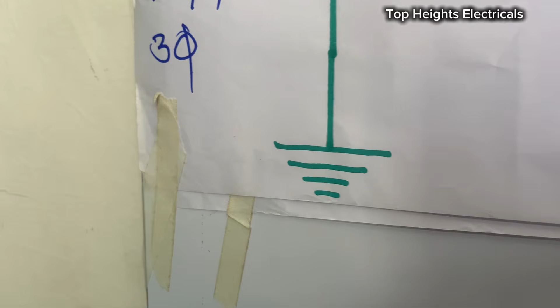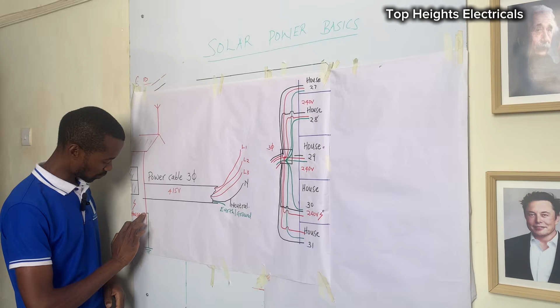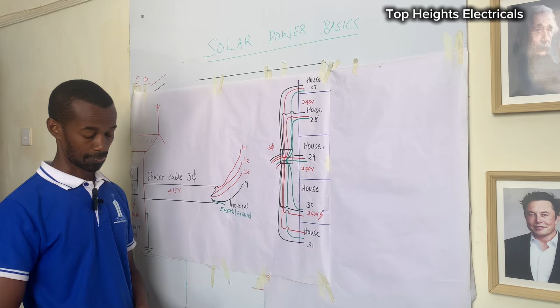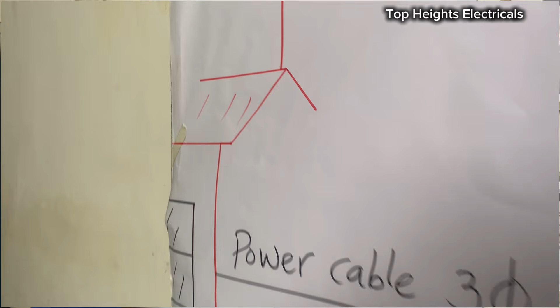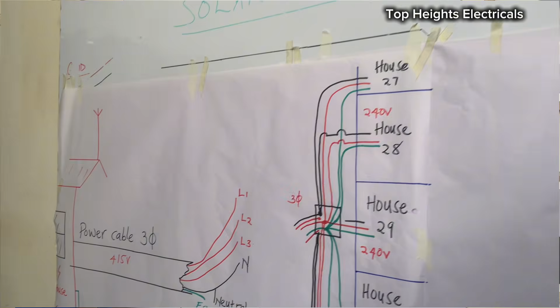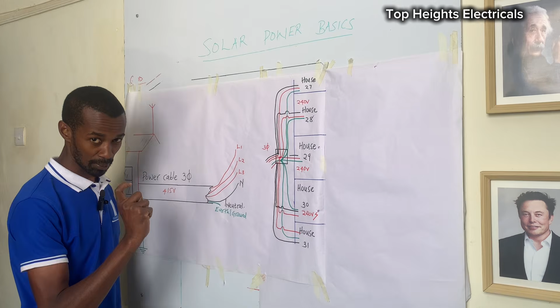My top boss, to demonstrate using a diagram here, we have a powerhouse somewhere. We were not able to see it, but assuming that this is the powerhouse in question, we have a cable all the way to the earth rod. And we have the three-phase cable traveling all the way from the powerhouse, very long distance, if you ask me, for this size of a cable. Because remember, we discovered that the size of the cable was too small. One of the contributing factors when it comes to the resistance of a cable is the length.